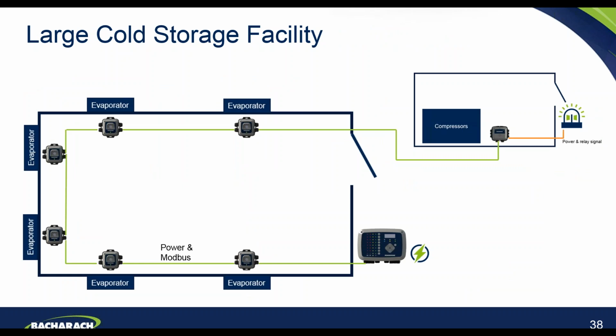So here we have a large cold storage facility, for example, with a number of detectors in a cold room, and also a detector in the machinery room at the top right there. And this particular one is nice because it highlights the daisy chain capability of the detectors connected into a control panel.